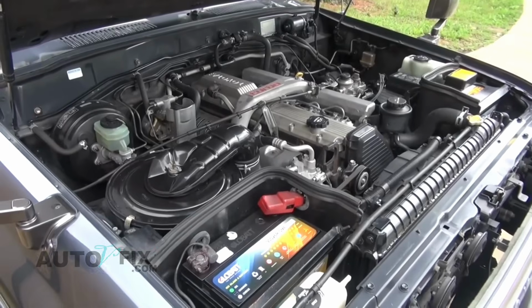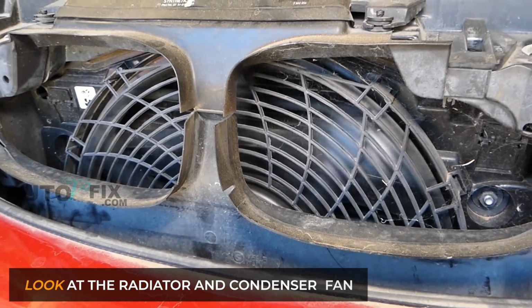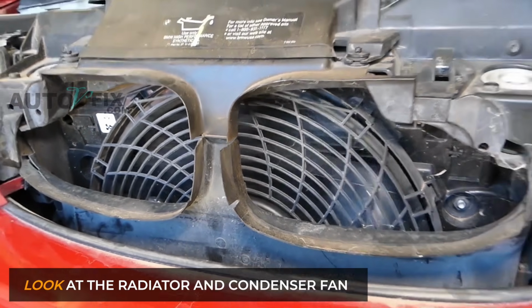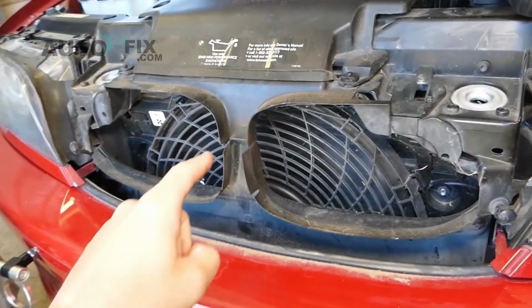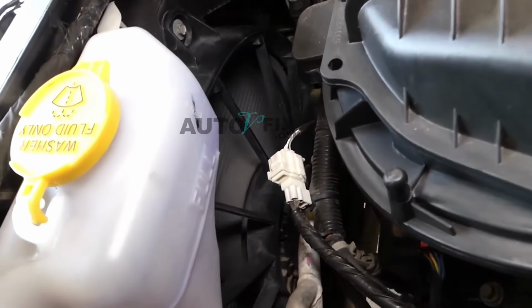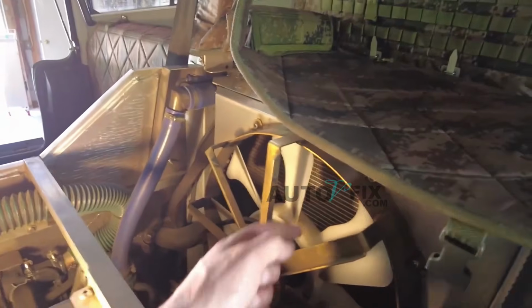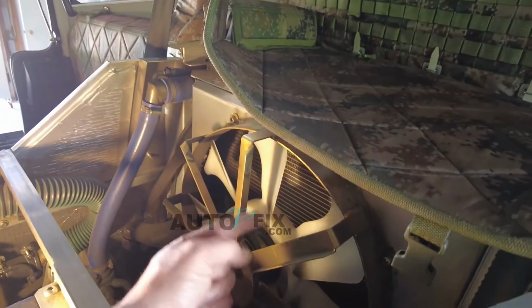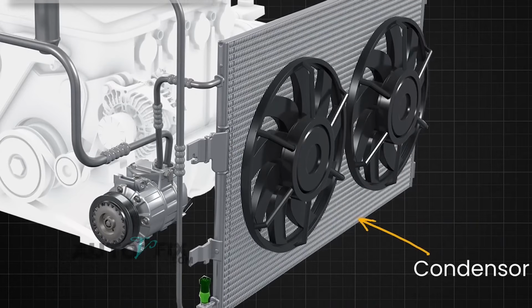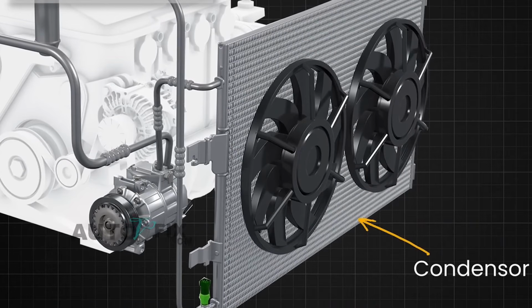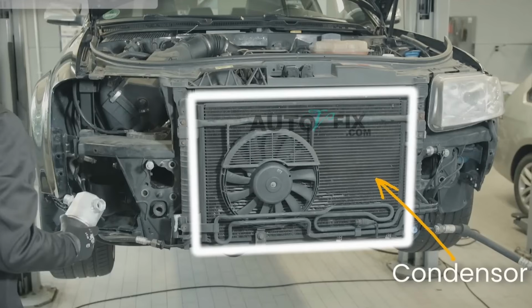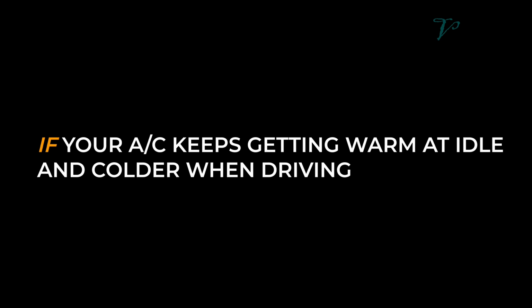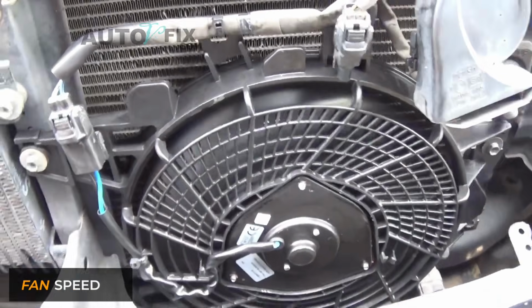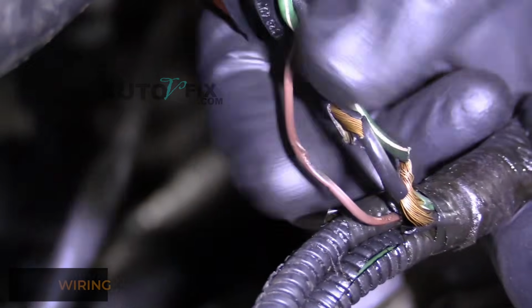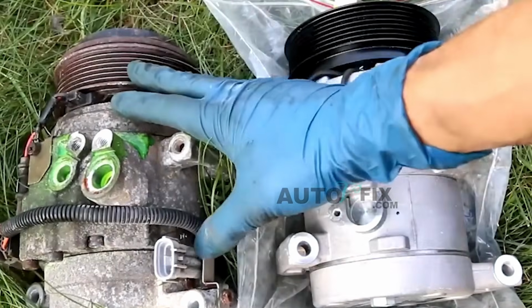With the engine running and the AC turned on, look at the radiator and condenser fan from a safe distance. Never put your hand, wire, cloth, or tool near the fan, even if it is not moving, because electric fans can start without warning. On many vehicles, at least one fan will run or cycle when the AC is on, although fan strategy varies by model. A stationary fan does not automatically prove the fan motor is bad, but if your AC keeps getting warm at idle and colder when driving, you should check the fan motor, fan speed, fuse, relay, control module, wiring, and condenser airflow before blaming the compressor.